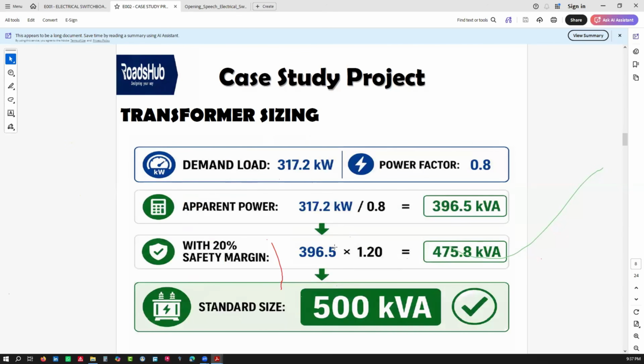Now, what is your transformer size? You know a transformer as a unit that is rated with a kVA value. So for you to change the kilowatt demand power to kVA, you need a power factor. And you really don't need to calculate that, because this power factor is given on the transformer data sheet or even the nameplate. So you just convert that to apparent power. But now remember, that transformer needs to have a safety margin of up to 20%. Actually, it's 20 to 30. We can do 25, we can do 20, we can also do 30, but it depends on your case. If it's an industrial setup, we do 30%. And this also depends on which standard you use, because all of these systems have standards we follow to guide us.